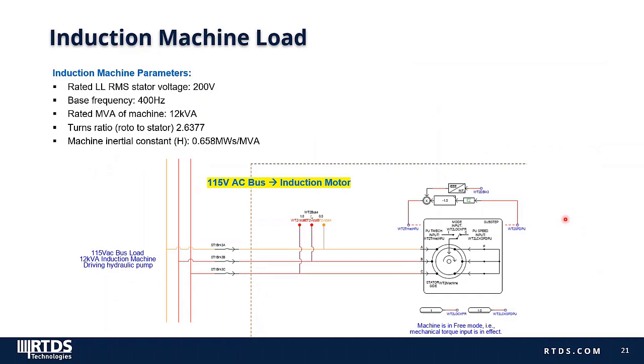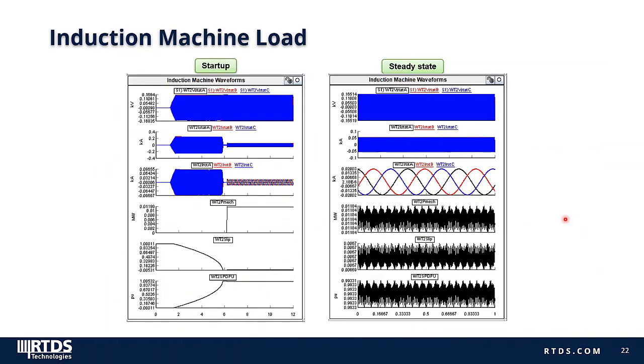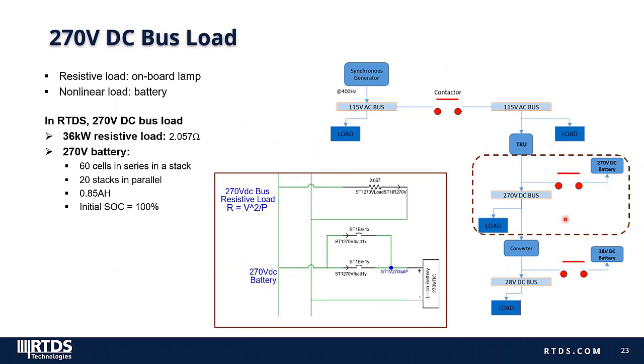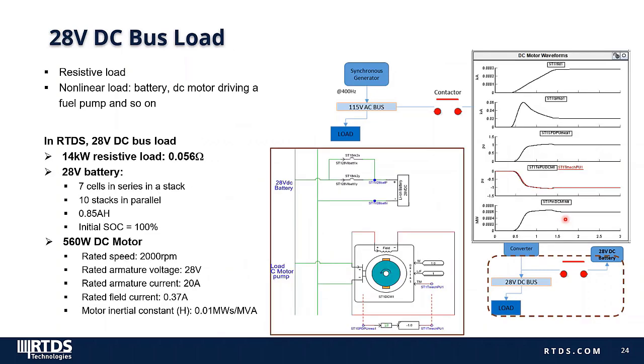There is also an induction machine load directly connected to the main AC bus, rated at 12 kVA. Simulation results show that the induction machine operates successfully at around 1 per unit speed in steady state. For the 270 V DC bus, a resistive load is considered for onboard lamps, along with battery support — the initial SOC of the battery is set to 100%. For the 28 V DC bus, a resistive load, battery support, and a DC motor are considered, the DC motor generally used to drive a fuel pump.